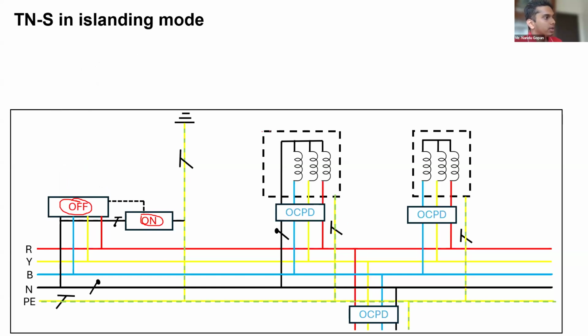So in this, not the transformer, the local source. From the local source, 5 wires are coming. So these 5 wires will be coming, and in the main distribution it will be like this. Since this is off and this is on, this is where the system referencing has been done. The neutral of the conductor and the PE of the installation have been connected here at a single point.